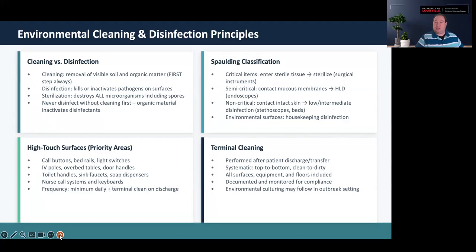Now, sterilization is sort of that final approach of let's get rid of everything with the exception of your prions, right? And so when you think about sterilization, it's only as good as it's done correctly and verified. So we can run stuff through sterilization and it could still fail. And if we don't monitor it, that's a problem. And I'll give you a pretty sad but dramatic example. And I won't say where it was, but it was here in Atlanta.